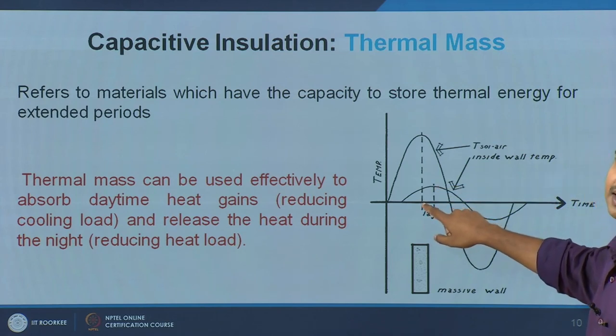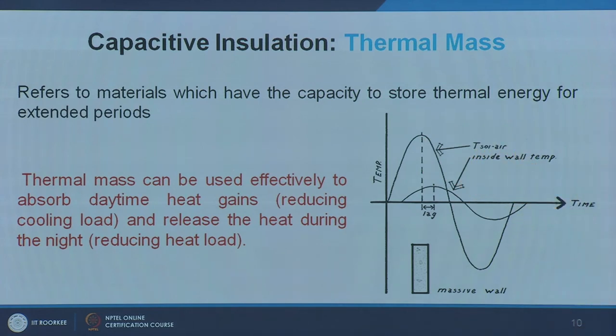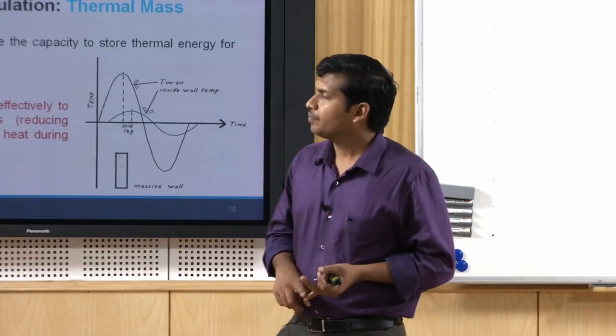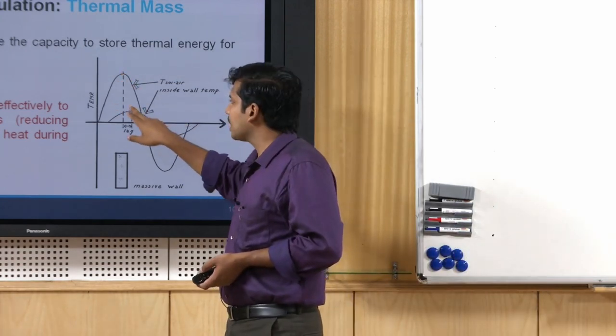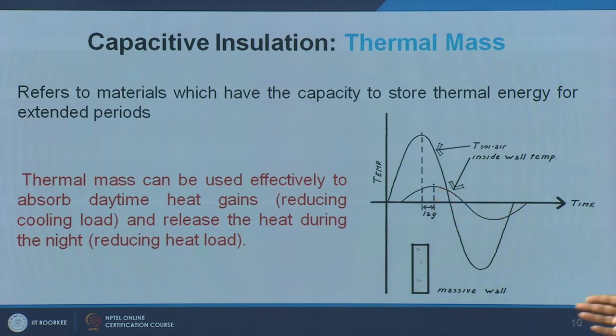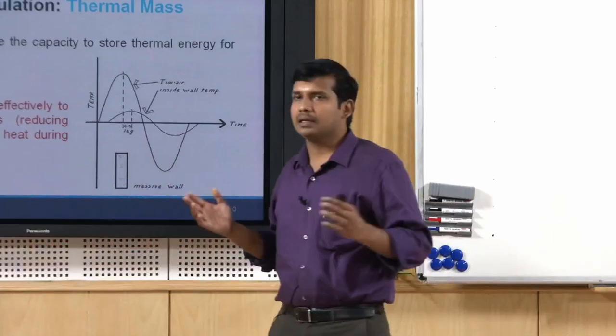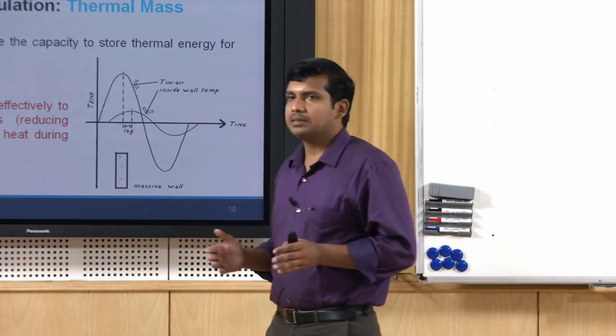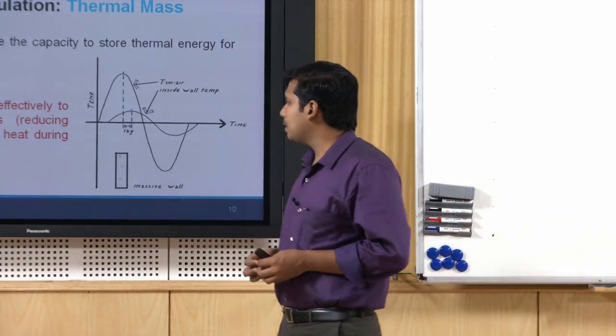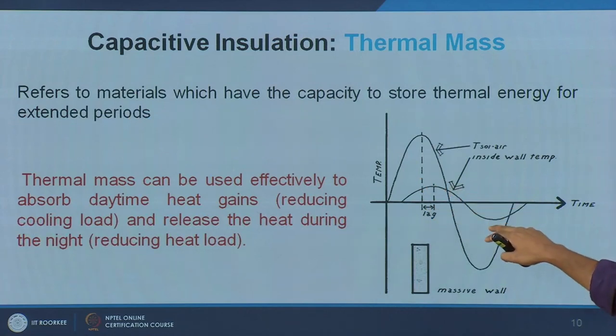The major parameter we look at based on capacitive insulation is time lag — how much time it takes for the indoor maximum to occur compared to the outdoor maximum. For example, if the outside peak occurs at 2 o'clock in the afternoon, the inside peak may happen 1.5 to 2 hours later for thinner walls, or as much as 4 to 5 hours for a thick adobe wall. However, the same effect also occurs at nighttime — it may be advantageous in some cases and disadvantageous in others.